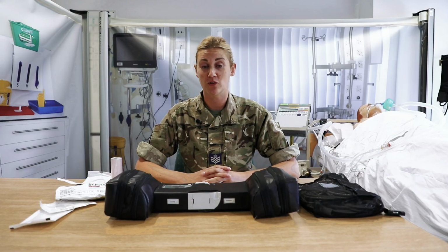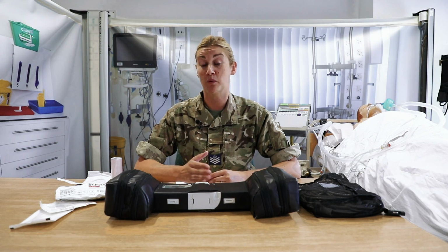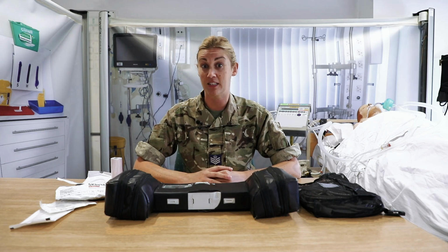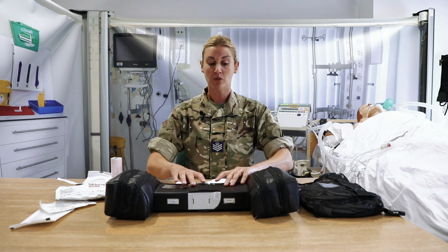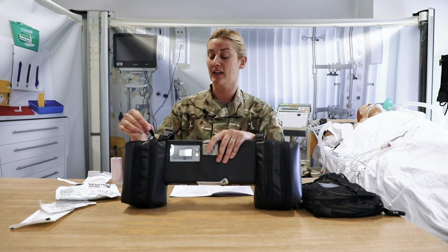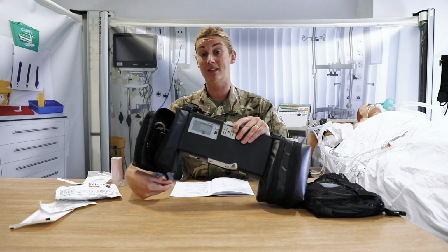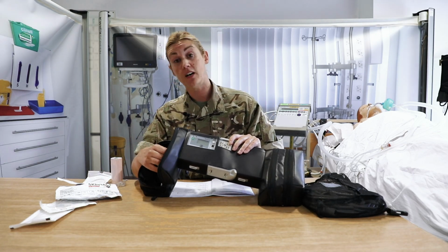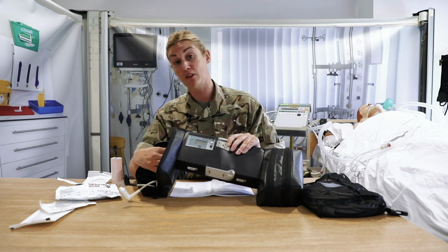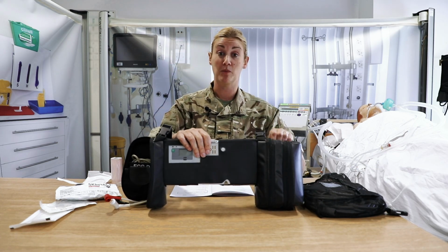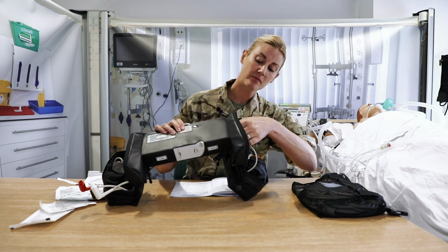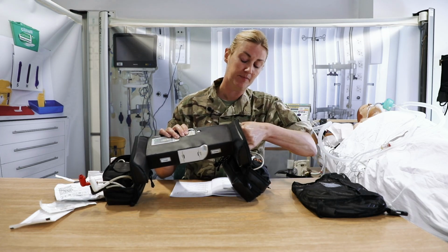We're going to go through the patient box. Now this is probably the most long-winded part because we're going to have to take out every single cable, make sure that it's good to go. And then when we move into the functional checks, some of those cables we're actually going to check physically that they work. So you'll notice that the patient box comes in its own bag. So first things first is to remove all of the plugs so that we can remove the box from its bag. So make sure everything's unplugged.